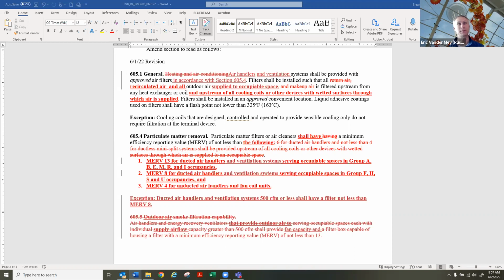Carolyn will probably mention it, but I was just reading Mike Moore's comment in the chat, moving it to say filtration prior to introduction to occupiable space. I think on first read, that might address what you're talking about, Eric. Well, but we're losing the requirement we had before for MERV 6 coming back, right? Yeah, there's probably a better way to write that. Maybe an exception where a MERV 6 filter is provided upstream of a heat exchanger. Yeah, I'll work on a sentence here. Okay, come back to me.